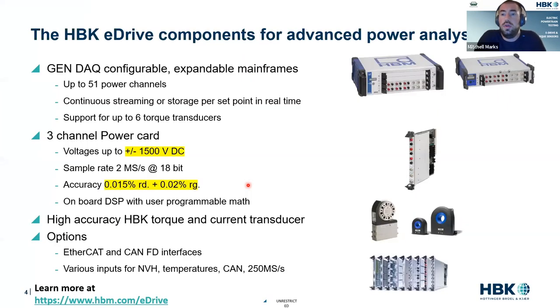Cool. So the power analyzer we speak about, and I do apologize for having this be a little bit of a product spec, is a measurement instrument. It's one of these boxes. We have several sizes of boxes, which allow us to measure up to 51 channels of electric power in one location. This means for 6-phase machines, 9-phase machines, multiple machines, multiple inverters, we can bring all of those measurements into one time-aligned location. This is really powerful for measuring larger, more complex systems or characterizing several systems at once.